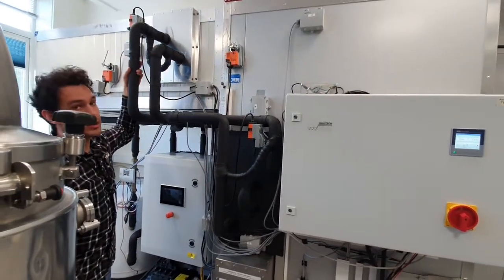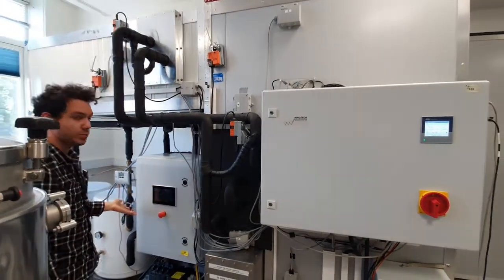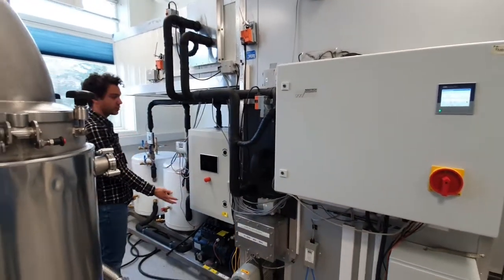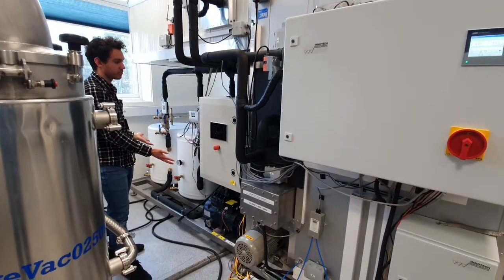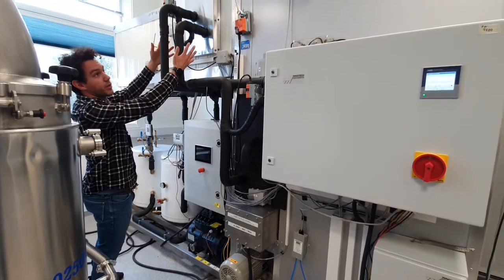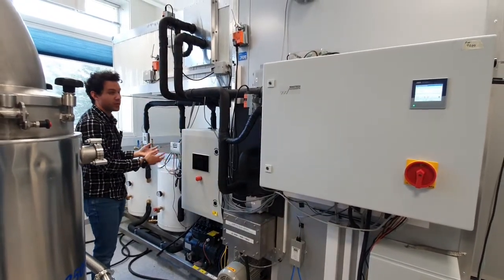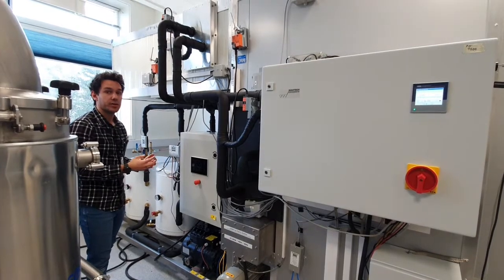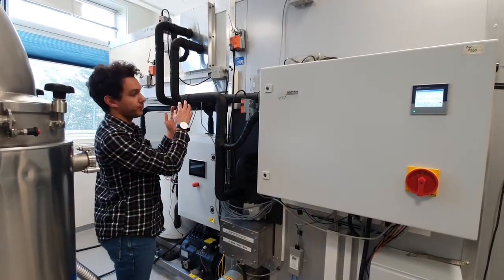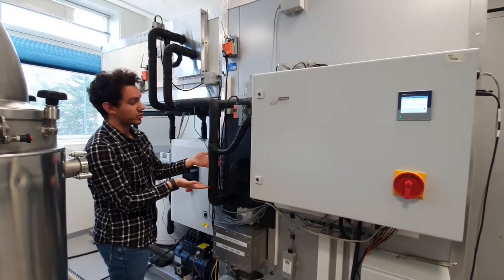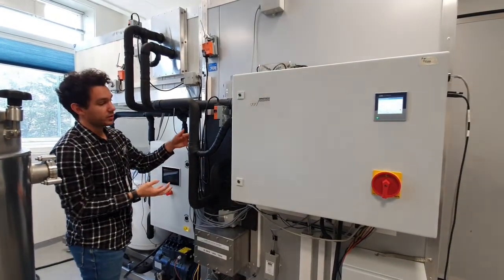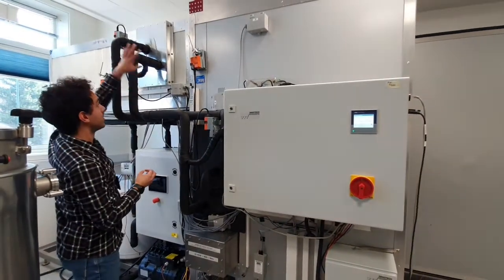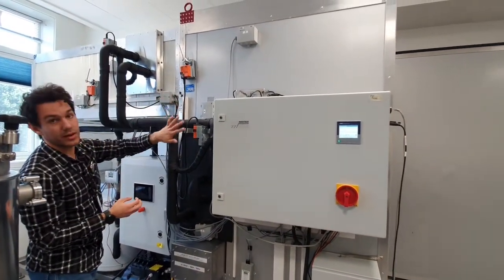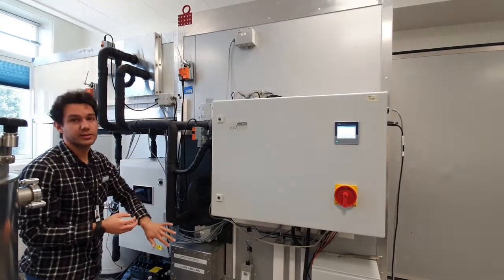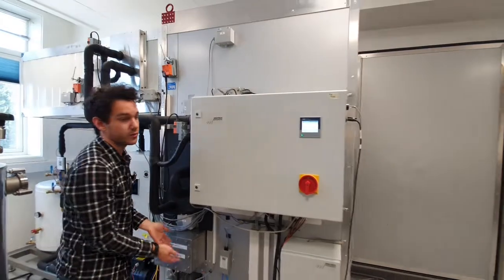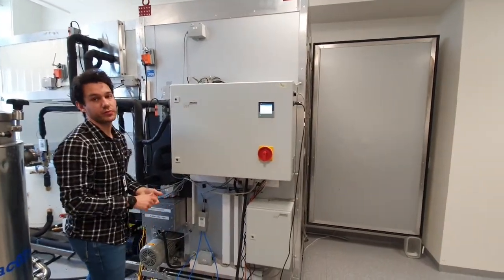This heat exchanger is connected to a CO2 heat pump installed below here. It takes the heat from the hot and moist air and upgrades it to a higher temperature, then inputs that heat via another heat exchanger located here, such that the air is cooled but then reheated to the correct drying temperatures needed to dry the products.